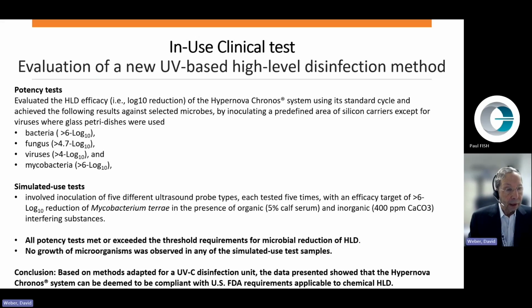This involved inoculation of 5 different ultrasound probe types, each tested 5 times with an efficacy target of greater than 6 log10 reduction of Mycobacterium terrae in the presence of organic, that is 5% calf serum, and inorganic, that is 400 parts per million of calcium chloride, calcium carbonate, interfering substances. All potency tests met or exceeded the threshold requirements for microbial reduction of HLD.